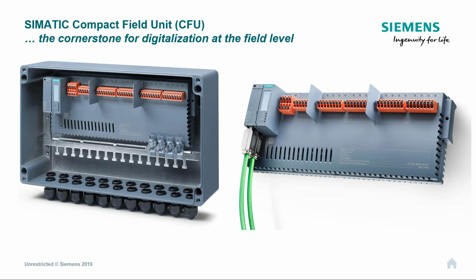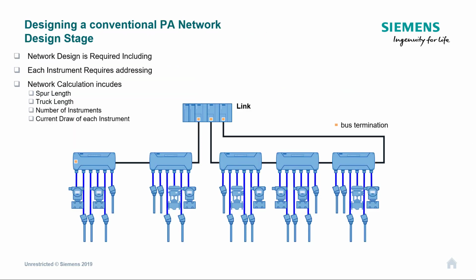There is a blog that I've done discussing Profibus PA and DP, so I'll put the link in this blog. But if we just refresh our memories on what we've got to do, we have a device converting Profibus DP to PA, and that has to sit in a cabinet, normally in a safe area, and then we use the high-powered trunk concept, either with one line or a redundant ring, to connect to boxes called active field distribution boxes.